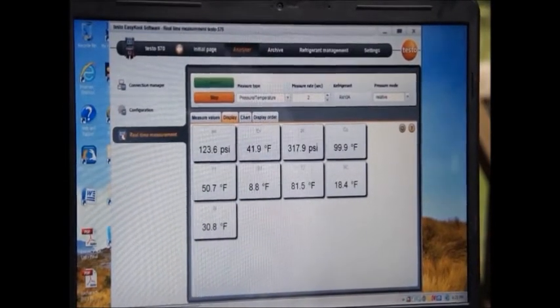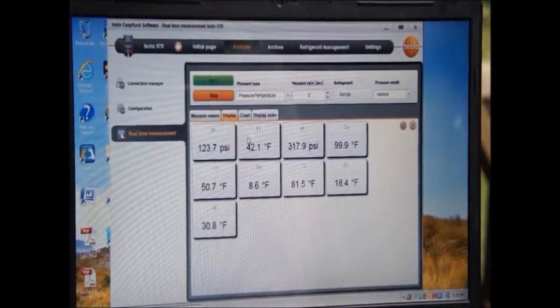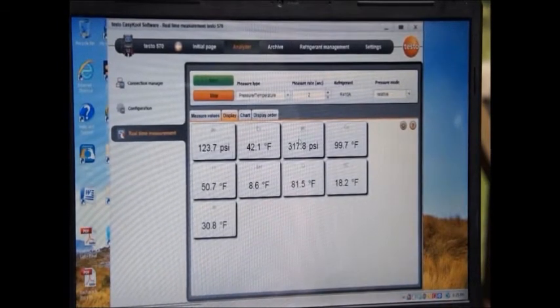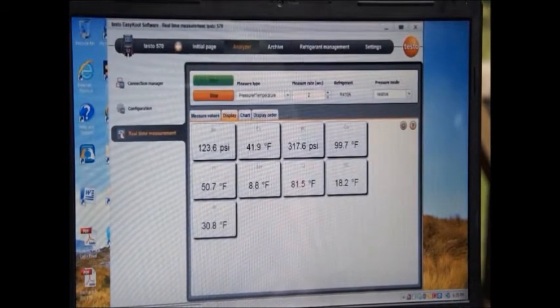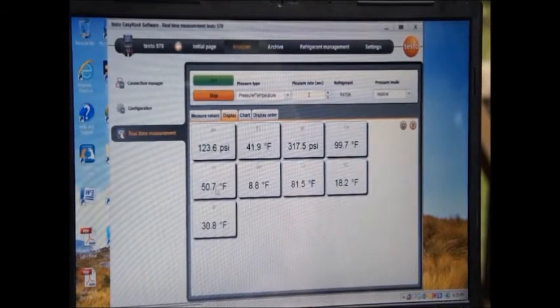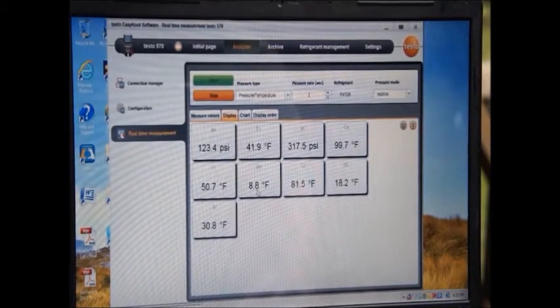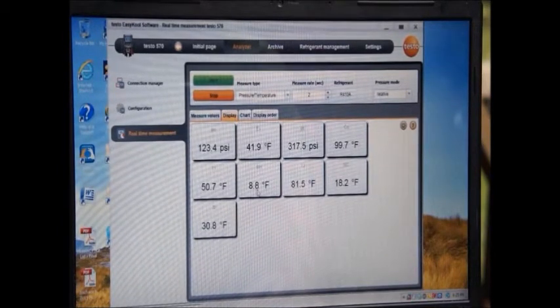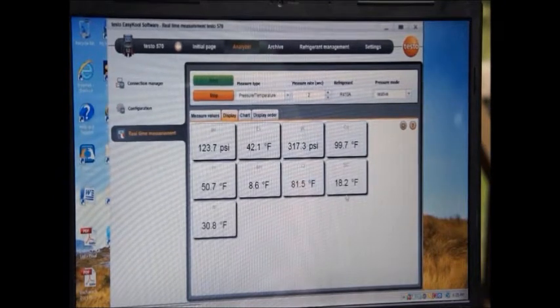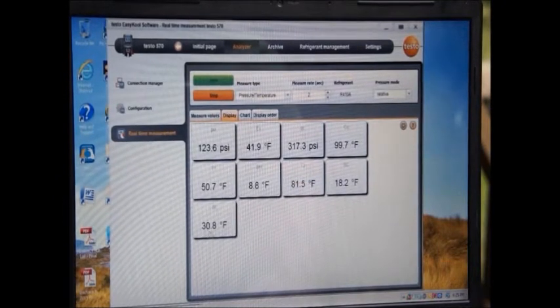I'm going to go to the display and you can see right here, now I've got all my icons on my display. I've got my pressure, my corresponding evaporating temp, my high side pressure, my corresponding condensing temp, temperature probe 1, superheat calculated off probe 1, temperature probe 2, subcooling calculated off probe 2, and then the difference between the two probes.